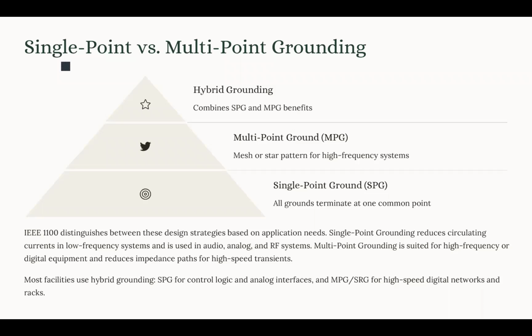Single point is sometimes preferred in a low frequency system because circulating current control is good in those systems, since it eliminates ground loops. It provides a clean reference, which is a single defined reference potential, minimizing analog measurement errors. But there is a limitation.